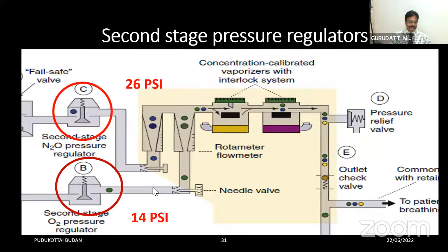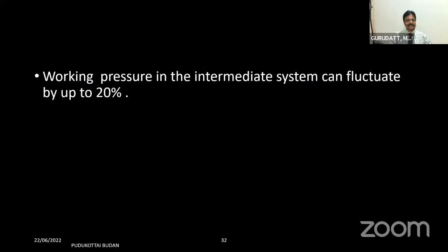Why the second stage pressure regulators are introduced in the GE machines is that, as long as the pressure in the system is reduced to less than 14 psig, the flow of oxygen will not alter. That means a very accurate flow will be there, because many times a lot of fluctuations can occur in the pressures of the pipeline as well as the cylinders.